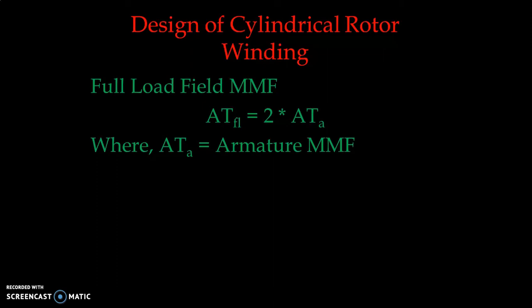The armature MMF (ATa) is calculated as 2.7 × I_phase × T_phase × Kw / P, where I_phase is the phase current, T_phase is the number of turns per phase, Kw is the stator winding factor, and P is the number of poles. For a synchronous alternator the stator winding design remains common whether it is a salient pole or a smooth cylindrical type of rotor construction.